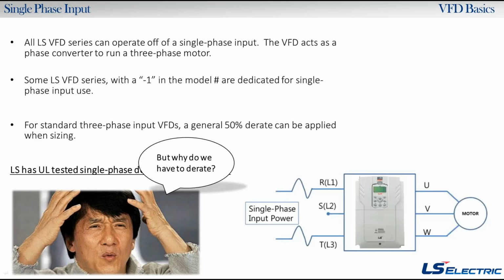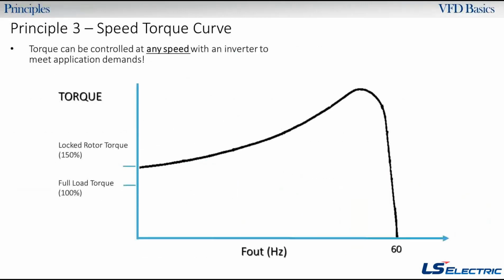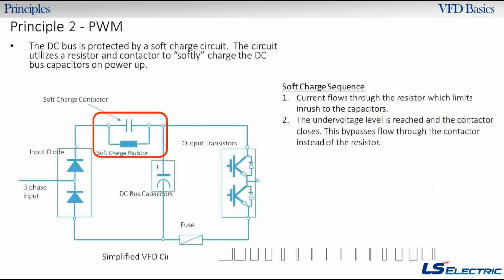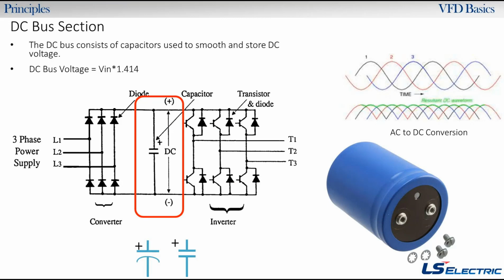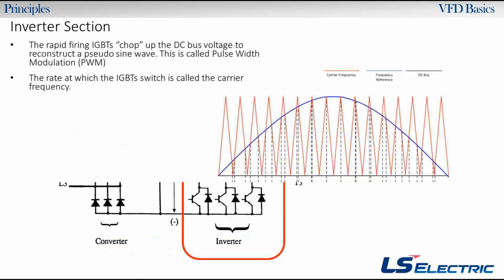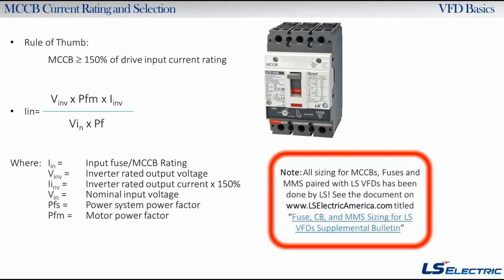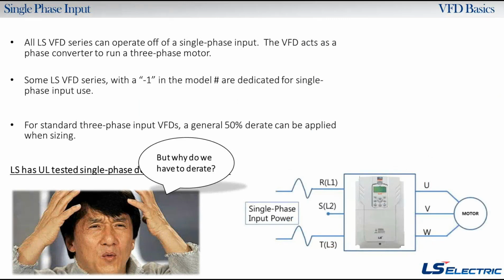And then also, when we double the size of the drive, we're also increasing the capacitance. So we're adding bigger capacitors, or maybe more capacitors onto that DC bus. That's actually going to help mitigate that DC bus ripple. If you go back to this slide here on the top right, you see there's phase 1, 2, and 3. You're not going to be using all those phases, so your DC waveform is going to have more of a bunny ears shape than this little ripple there. So there's more gaps in your AC to DC conversion, and those gaps are not the best for the capacitor, so you want to oversize the capacitors. By picking out a bigger drive, you're oversizing the capacitors, you're smoothing out the DC bus, and the drive's happy. You could technically run a non-derated drive, it's just not going to last very long. So make sure you do the proper derating.